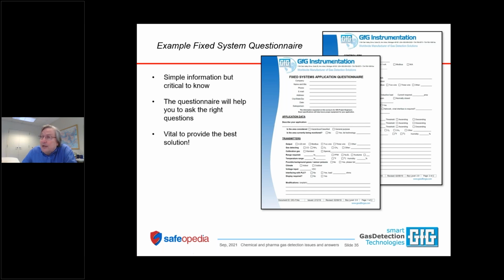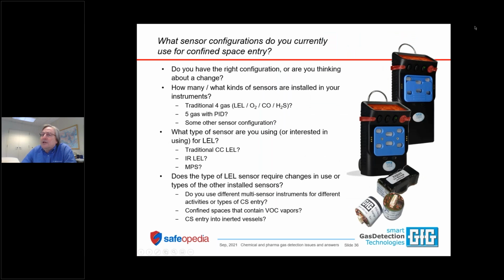Do you want to wire it by integrated, by digital means, by Modbus, by HART? Do you want to connect the gas detectors with the controllers by means of a 4 to 20 milliamp loop connection? Do you even need a controller, or do you already own a PLC? If some of these terms you don't know what that means and you've never heard those terms before, don't despair. That's why you have friends at the manufacturer and friends at your integrators and distributors to work with who do have the vocabulary and who can help you through the process of filling out that questionnaire.